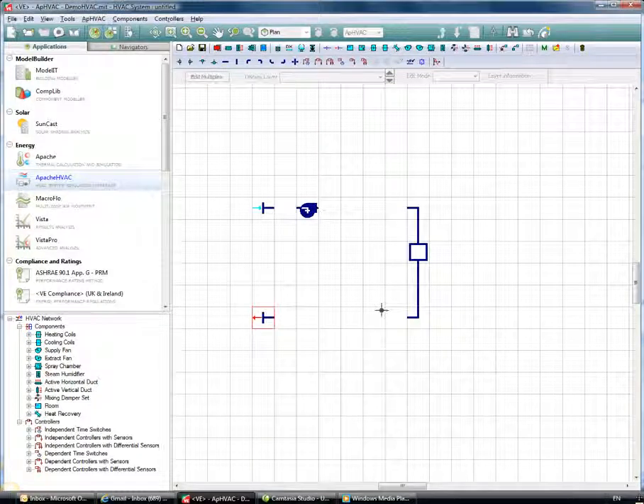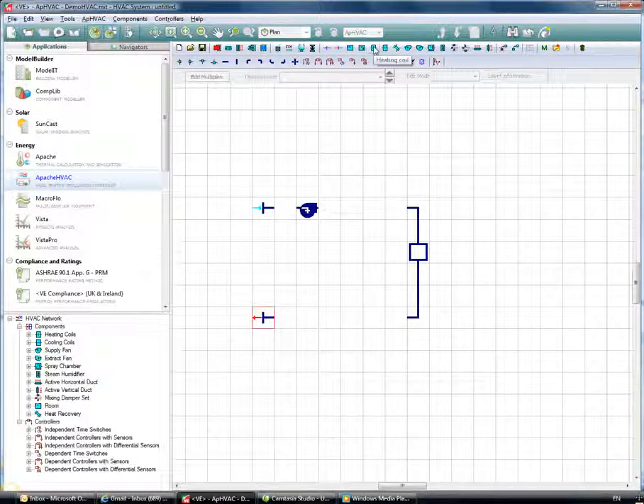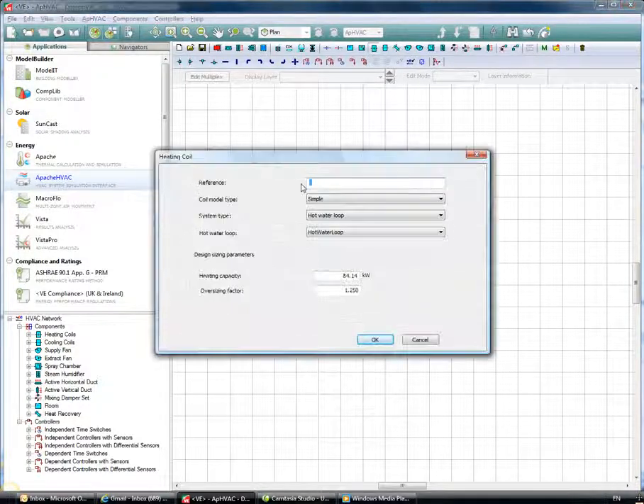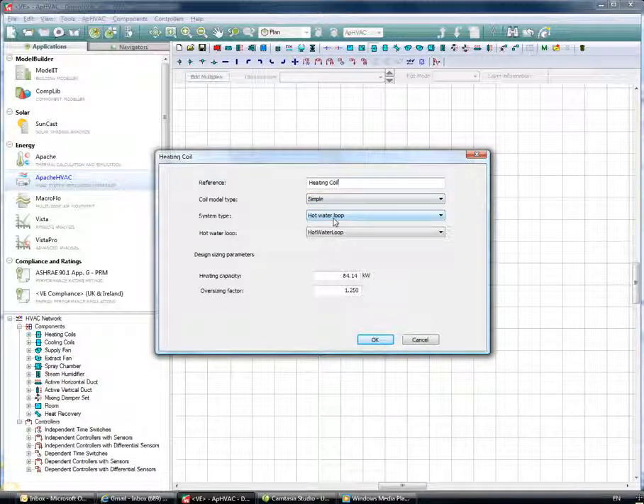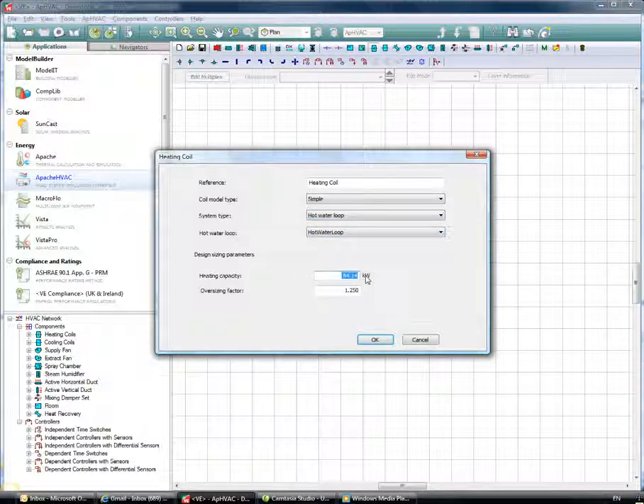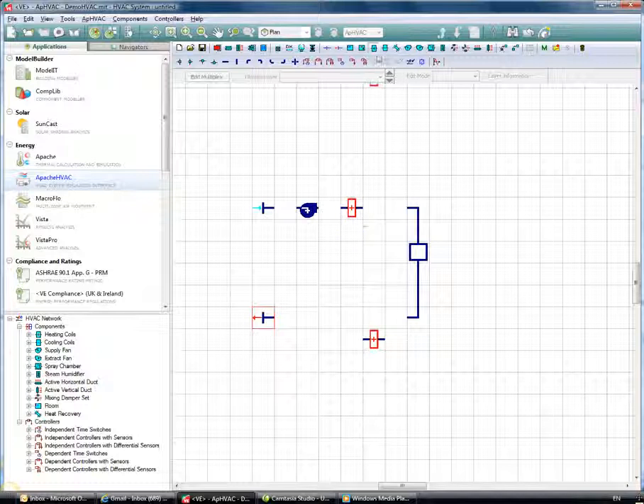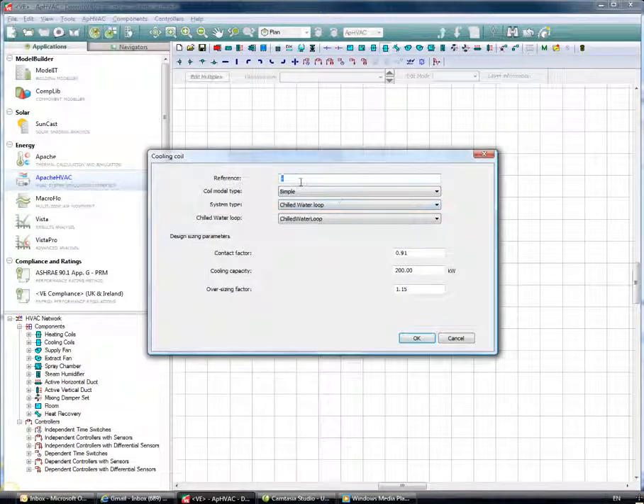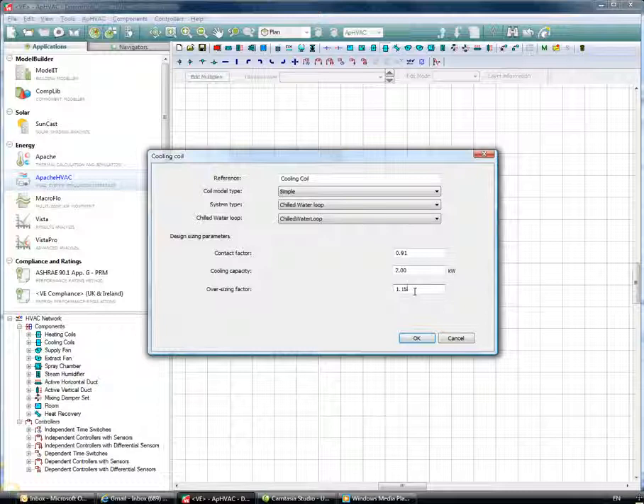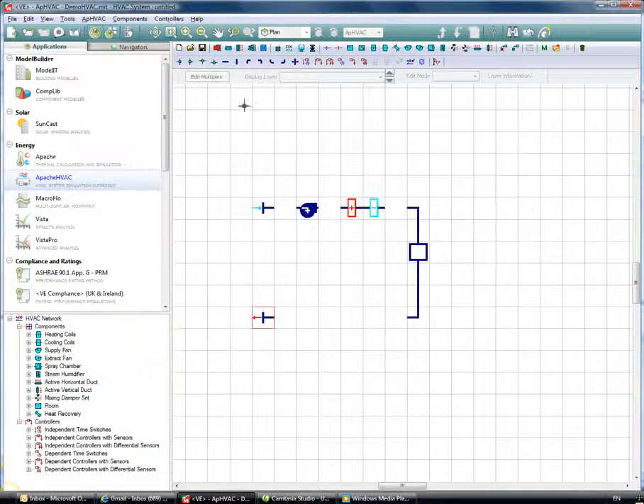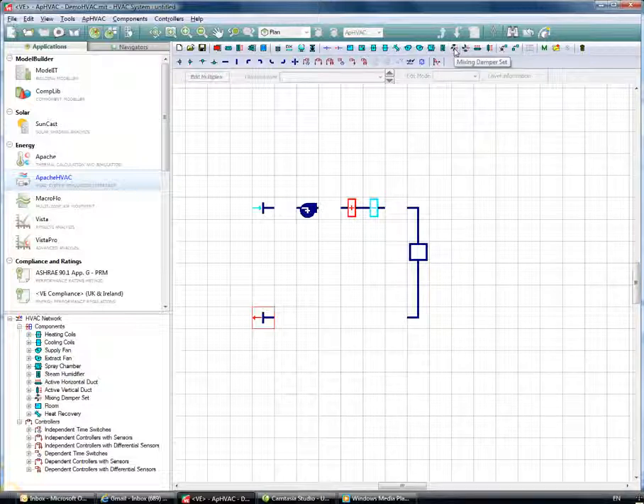Now that we have our heating and cooling sources in place, we can define our heating and cooling devices. I'll add a heating coil, call it 'Heating Coil', keep it as a simple coil model, set the system type to hot water loop as defined, set the capacity to 2 kilowatts, and leave the oversizing factor at 1.25. Then I'll add in the cooling coil, set the capacity to 2 kilowatts, and leave the oversizing factor at 1.15.